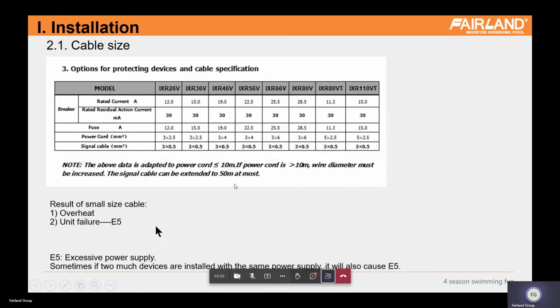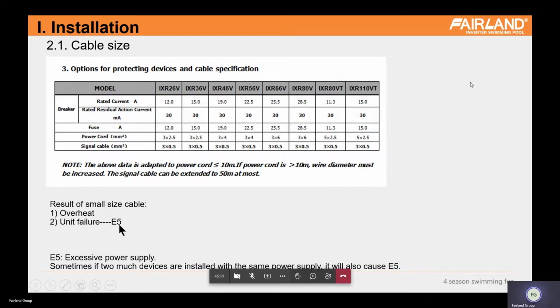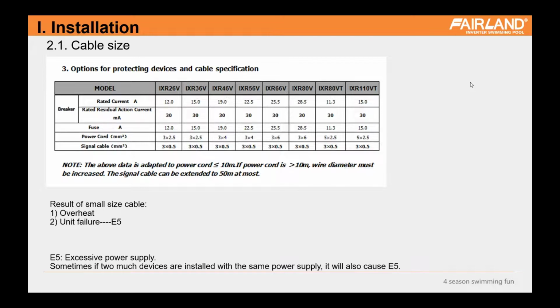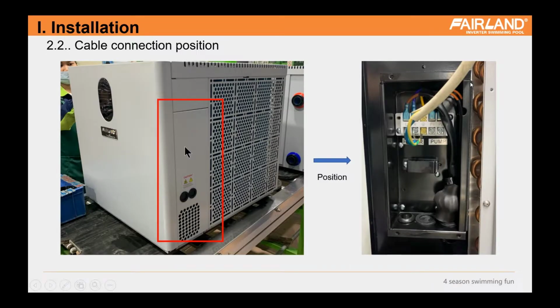One customer used a smaller size cable, I don't know why, but it caused unit failure, E5, which is excessive power supplied. And after he replaced it with the recommended size power cord, it recovered and went back to normal. And here is the position. Sometimes the customer cannot find the position of the wire connection, so we also show photos here for your reference.